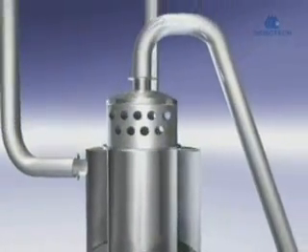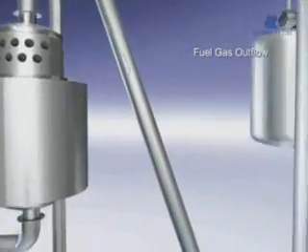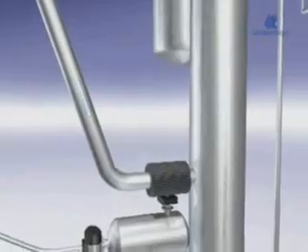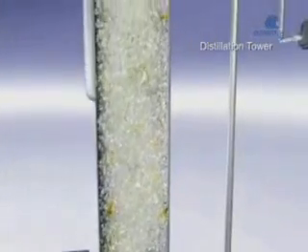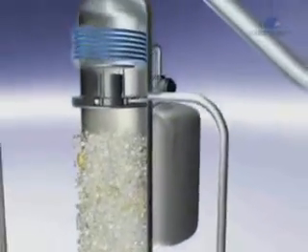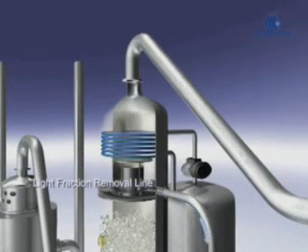Now, let's follow the gas line and see the processing of the light fractions and non-condensable gases. From the catalytic converter, the fuel gases flow through to the distillation column. Only fractions in the C8 to C25 range are condensed to the main fuel line. High volatile fractions are captured to form a light end product with similar properties to common degreaser. This valuable product is stored in its own tank.